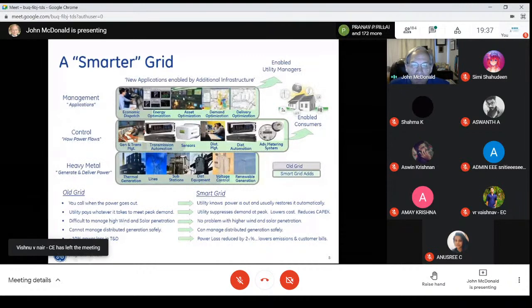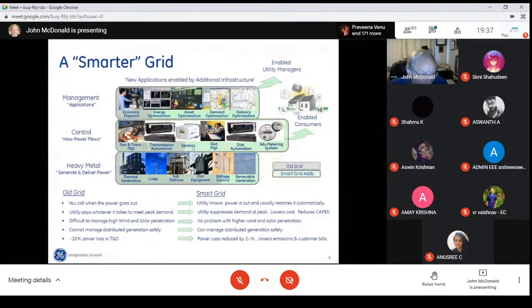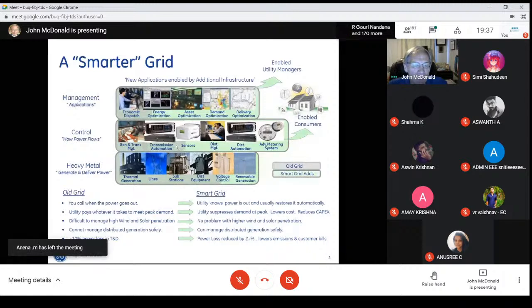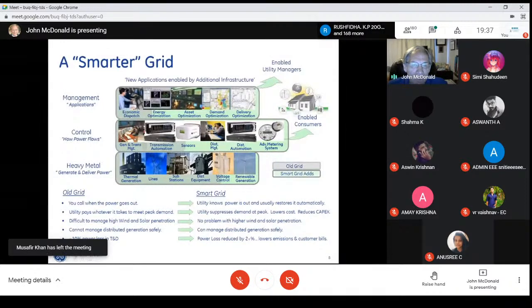Let's move to distribution management. I'll talk about this a little bit in terms of what we call a distribution management system. The distribution part of the grid is becoming much more complex with the integration of distributed generation. And we need a separate SCADA system to manage that complexity, and that's called a distribution management system, or an advanced distribution management system, a DMS or an ADMS. Then we get out downstream of the substation on the feeders. This is distribution automation, and then smart meters, and we'll talk more about smart meters, okay?